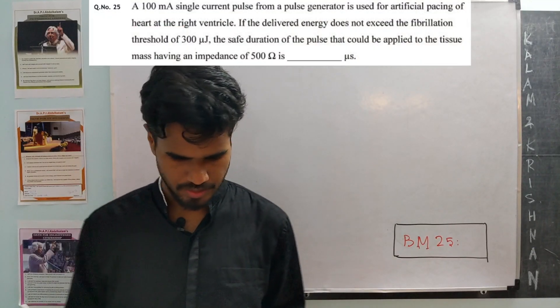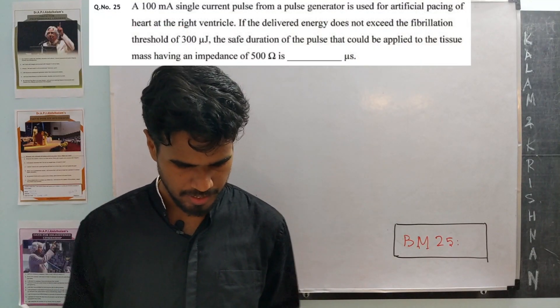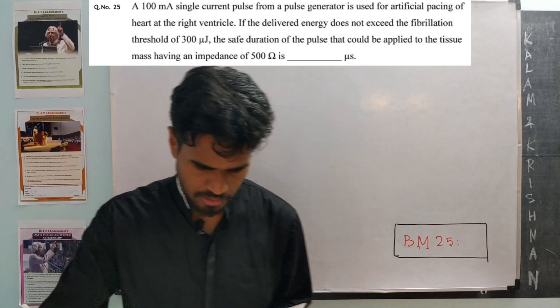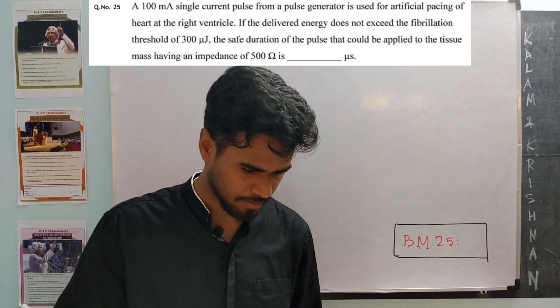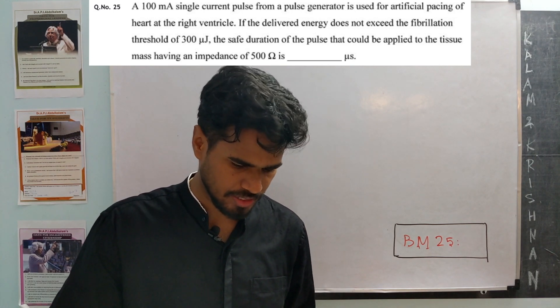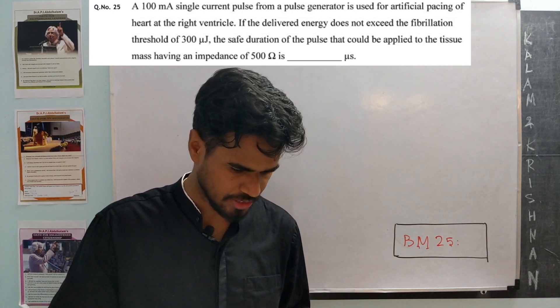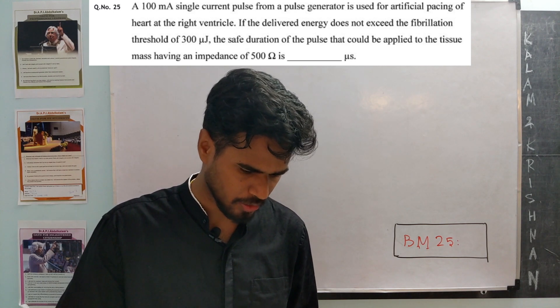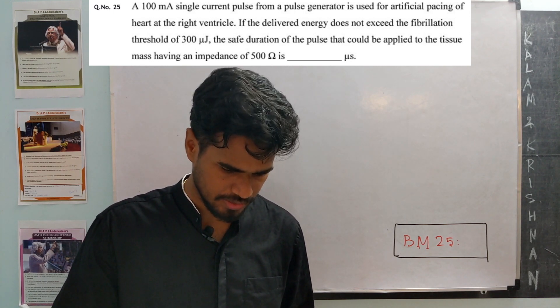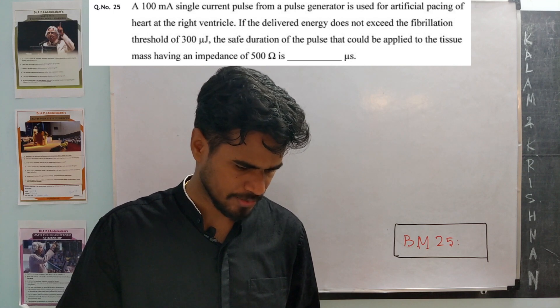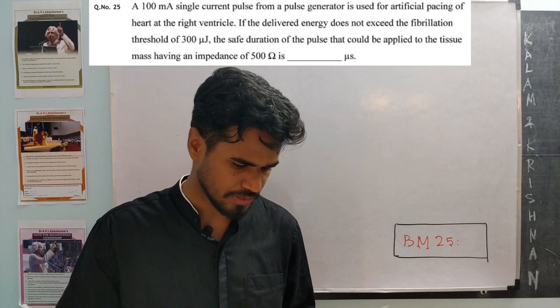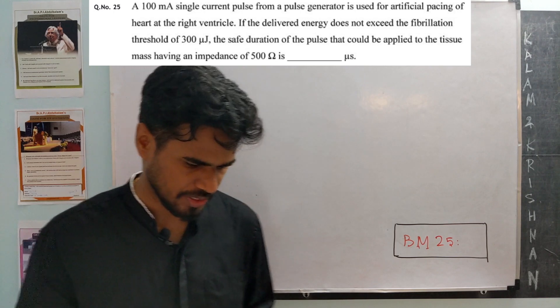Question 25: A 100 milliamp single current pulse from a pulse generator is used for artificial pacing of the heart at the right ventricle. If the delivered energy does not exceed the fibrillation threshold of 300 microjoules, the safe duration of the pulse applied to a tissue mass having an impedance of 500 ohms is how many microseconds?